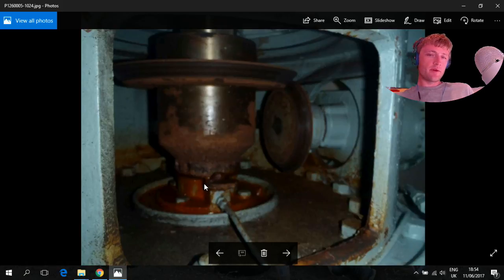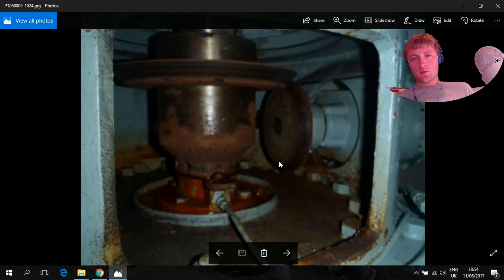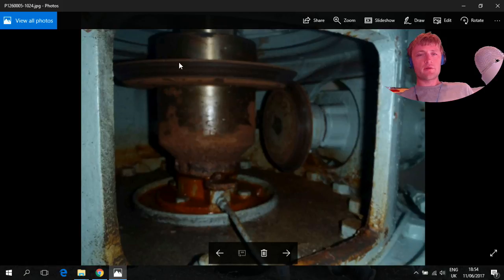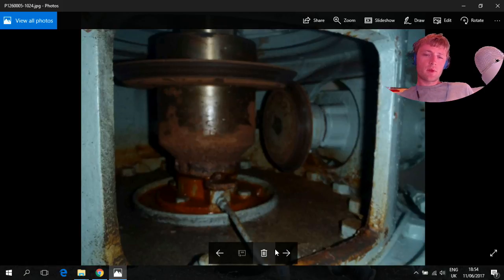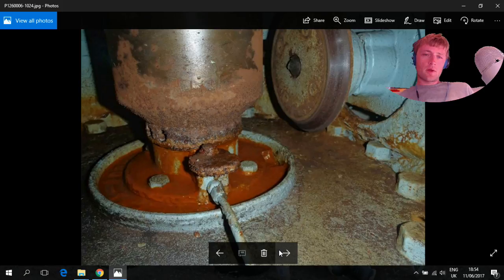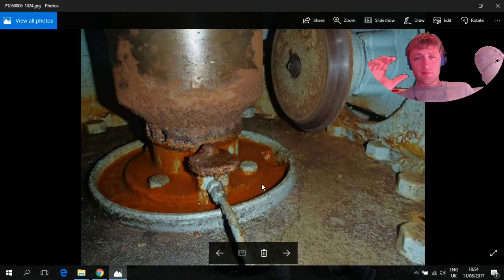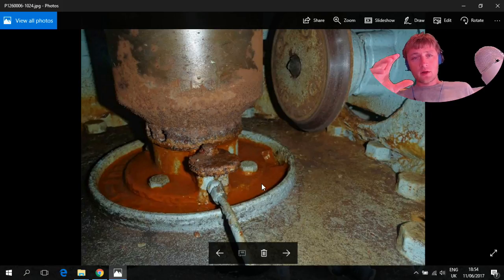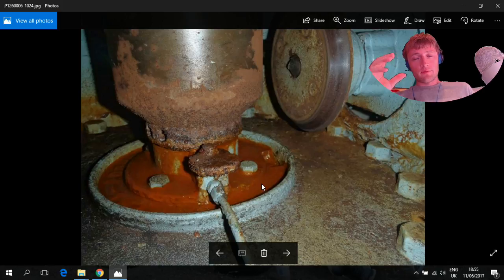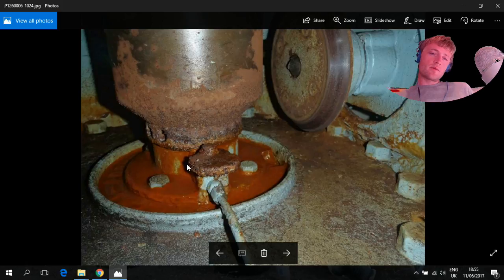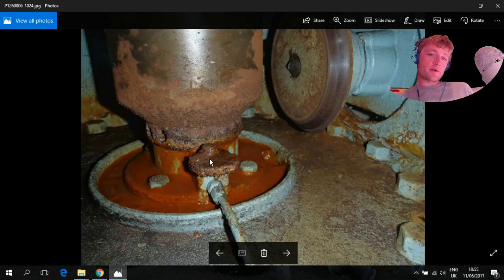Also there was a job to check this vacuum pump which is driving, as you can see, from the main shaft of the pump. It's similar to the video I have made for the main fire pump. These are the holders which must be cleaned from the rust.